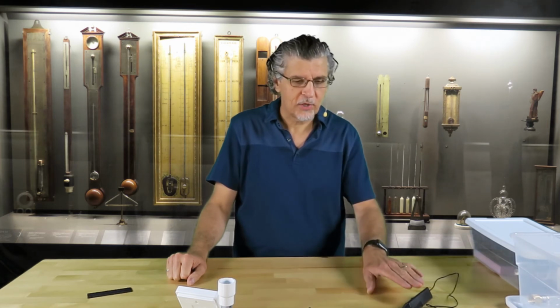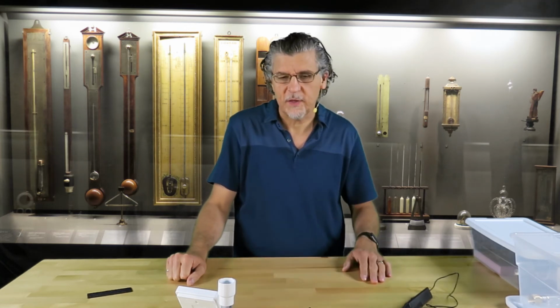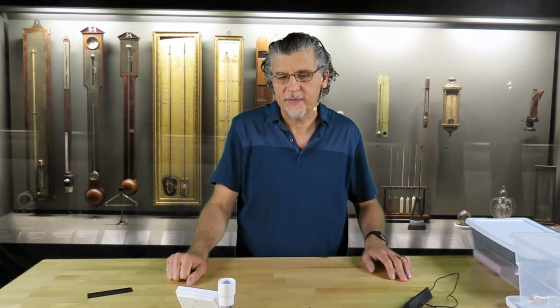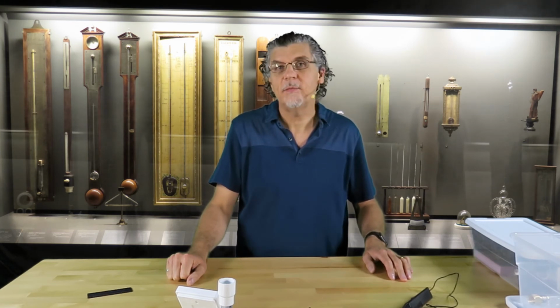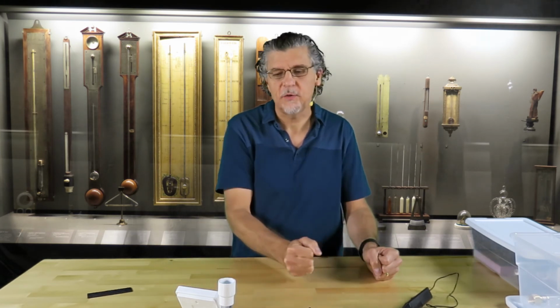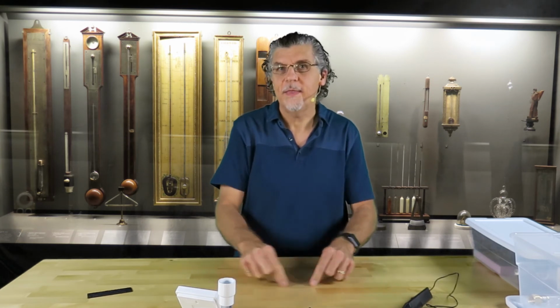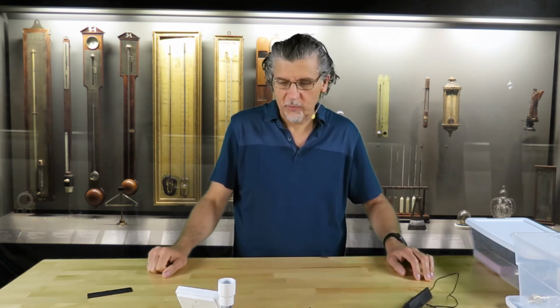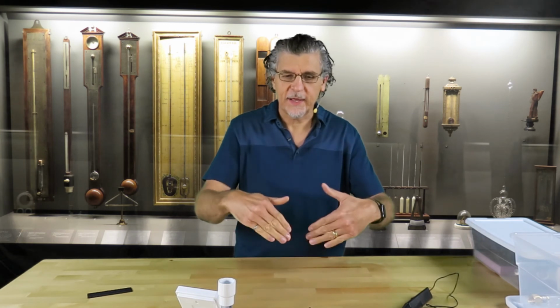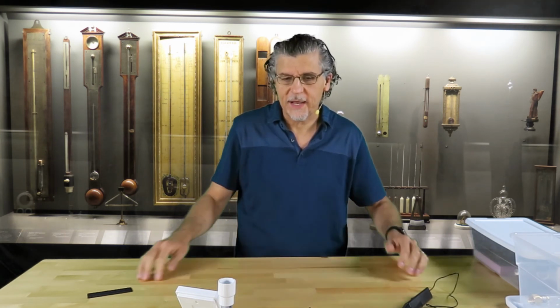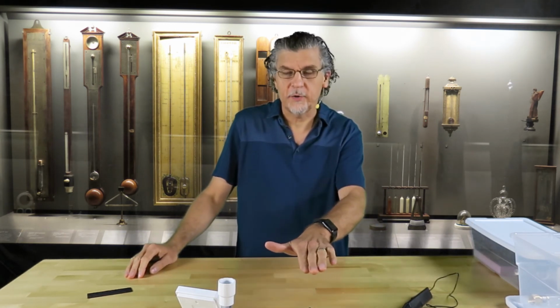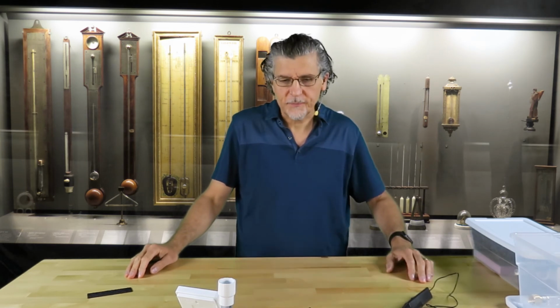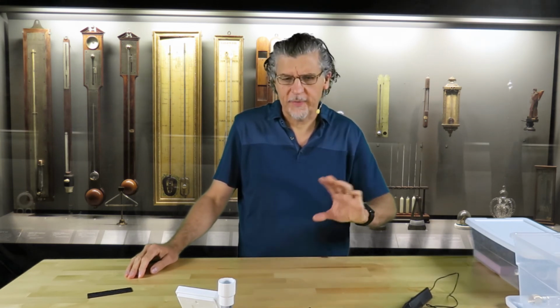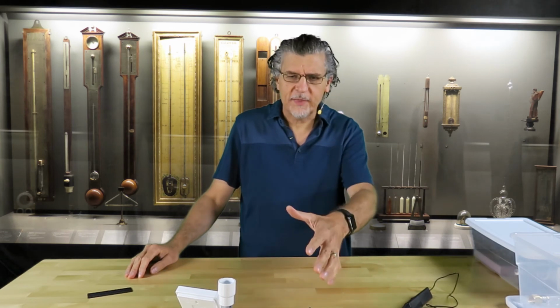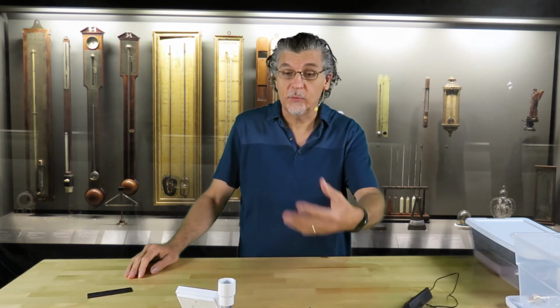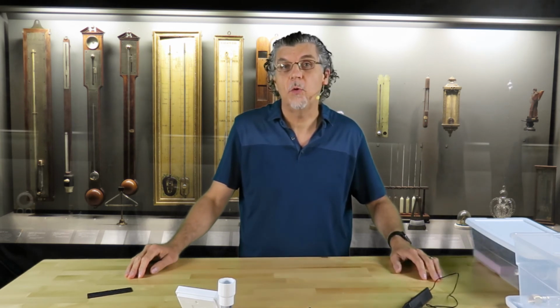And that's why it's a good idea to keep the temperature sensors in order in the way that they're placed inside of the calibration apparatus, and that'll make it easier when you read temperature 1, 2, 3, 4, and 5, and that will become one of the rows in your spreadsheet. And then you'll go to the next minute and you'll do it again and again and again. And we'll let the water cool to room temperature. And after we perform that part of the experiment, then we'll empty out the calibration unit and we'll repeat the experiment, but this time we'll use cold water.